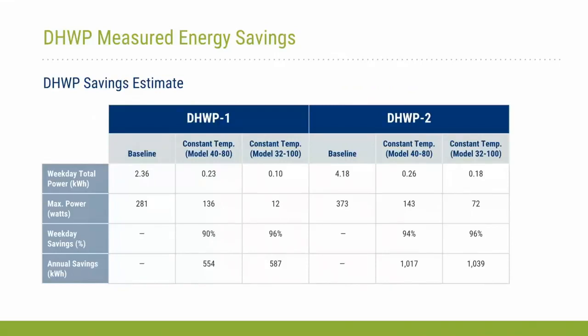So the measured energy savings that we got for domestic hot water pump number 1 was 90% for the 4080 and 96% for the model 32100. For domestic hot water pump number 2, you'll see the energy savings percentages were really similar there. The total kilowatt hour of savings for domestic hot water pump number 2 were roughly twice as high as the other one. And the reason for that was the flow rate and the load that one was serving was about twice as high, because again, it was pumping that domestic hot water fluid up to the 8th floor of the facility. But as you can see here, we had greater energy savings than we were anticipating on these, due to the pumps being more efficient and then also being able to ramp down during their operating period.